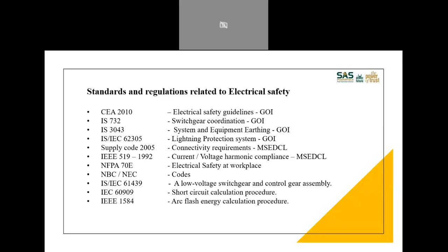IS 3043 is our system and equipment earthing standard in India. IS/IEC 62305 is the lightning protection system standard, again Government of India. Henceforth you will keep seeing IS/IEC because recently the Indian Standards institute has come to an agreement with IEC that IEC standards can be adopted as they are in India. So the standards will be called IS/IEC, and the same standard will become applicable in India as well. So most of the standards henceforth will come as IS/IEC.